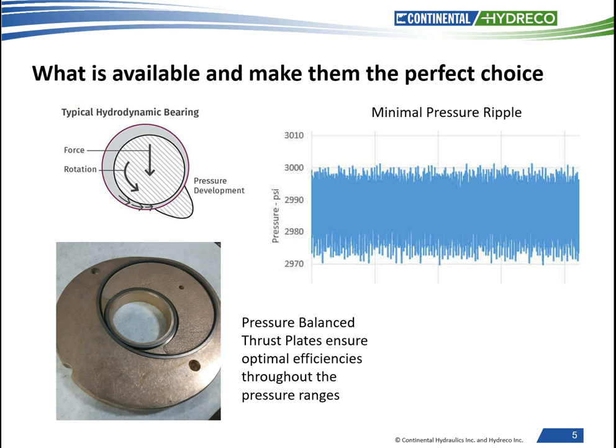As in all pumps, wear occurs as soon as the pump is put into service. One of the vane pump's advantages over a piston pump is they compensate for wear. For example, as a vane tip wears, they simply extend further out of the slots. Wear on the side plates occurs due to the ring movement, but the pressure balance thrust plates move to keep the efficiencies the same. Whereas in a piston pump, normal wear and tear means pistons in the barrels may wear out and they don't grow to compensate. Another common concern: they're only rated to 3000 psi where a piston pump is 5000 psi or more. For systems that require continuous operation above 3000 psi, a piston pump is the correct choice. But don't confuse the higher pressure capabilities with better performance or life in systems that require 3000 psi or less to do the work.